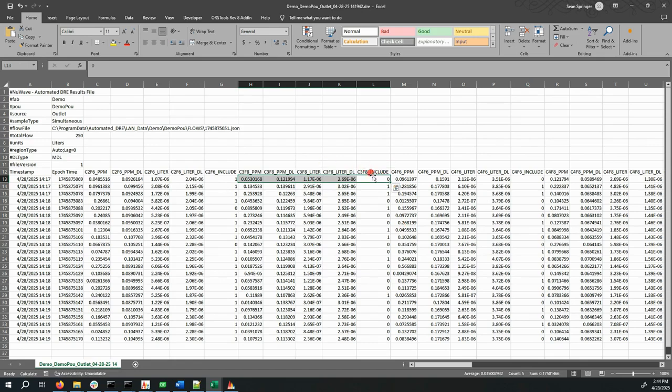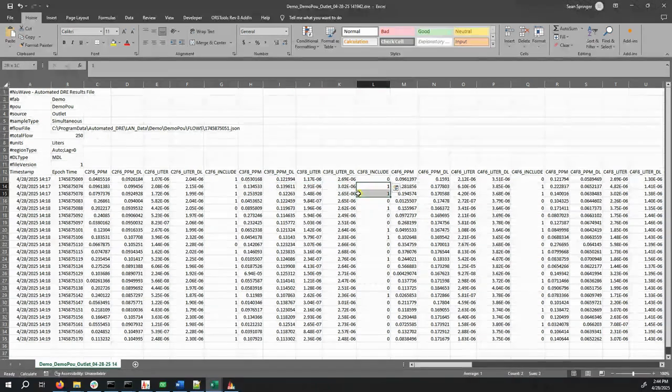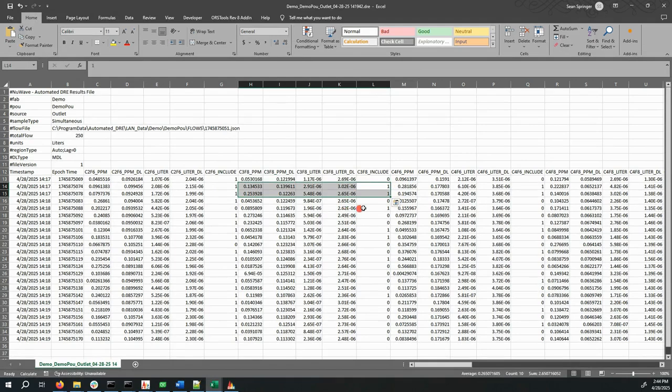And so it automatically chose, it said this one is BDL at the inlet. These two were not BDL at the inlet, so we would use these 2 points in the calculation and so forth. And hopefully you can see, with a little Excel functions, you could easily recalculate this DRE from the data presented here.